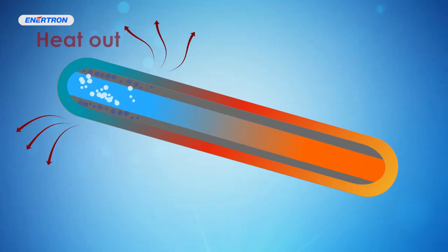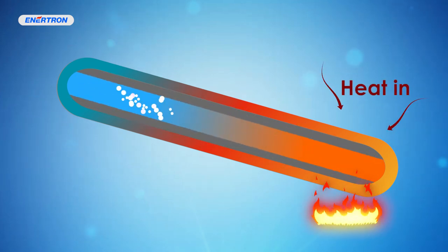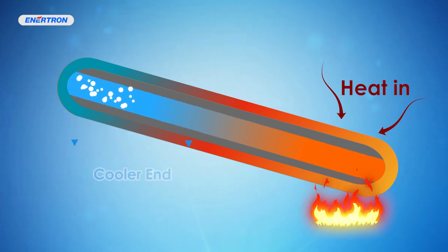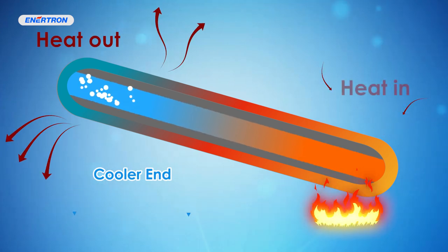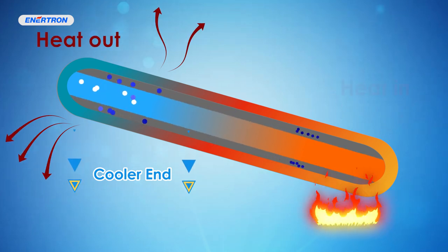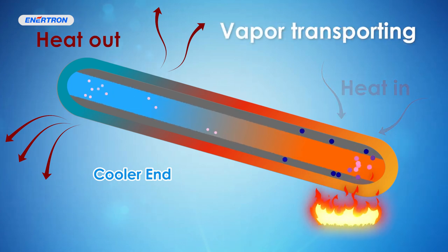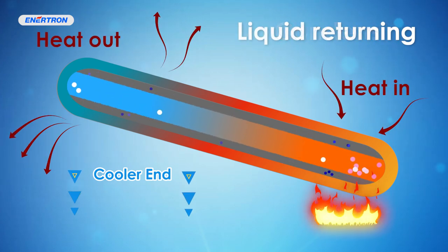The condensed liquid then travels back to the origin end of the pipe via the wick structure. Overall, a heat pipe cycle has four phases with each of these phases playing a role in the heat pipe's ability to transport heat from one end of the pipe to the other. The four phases are evaporating, vapor transporting, condensing, and liquid returning.